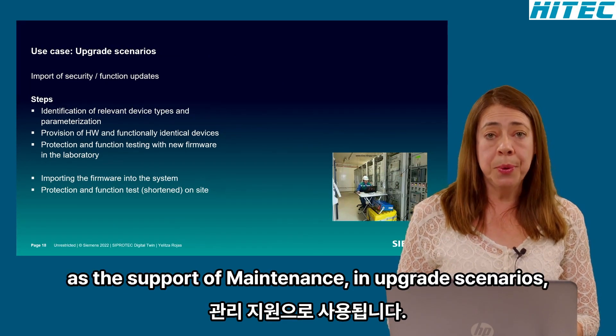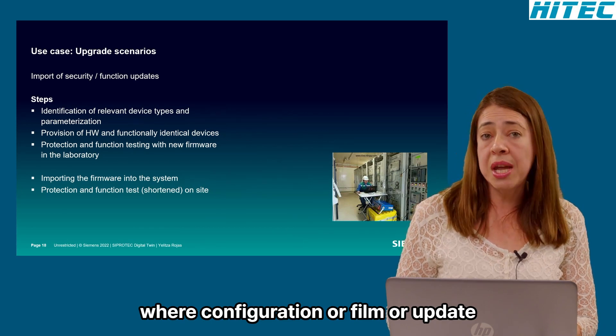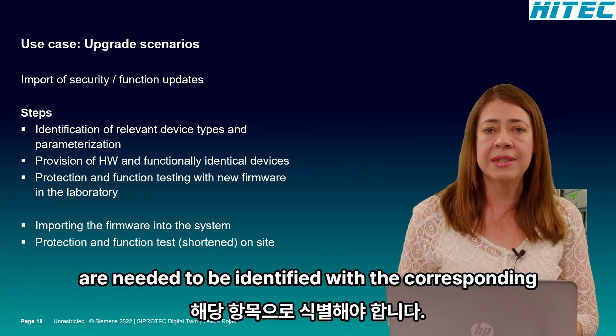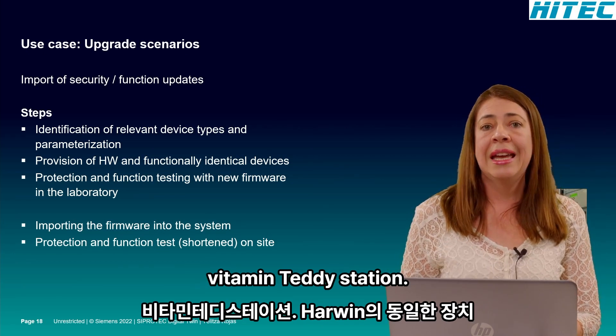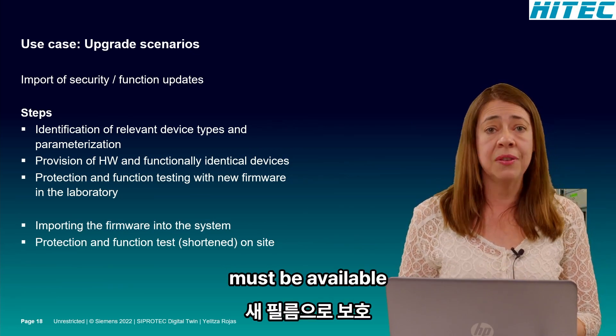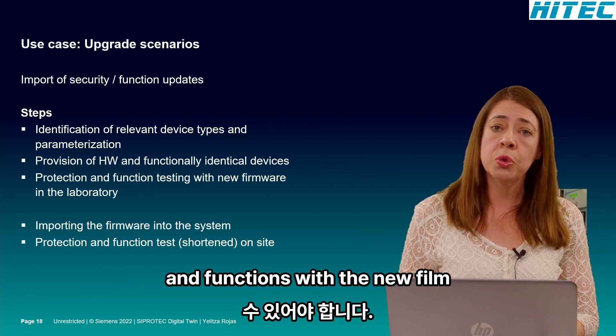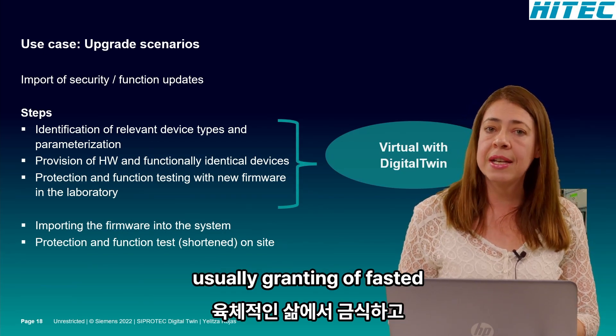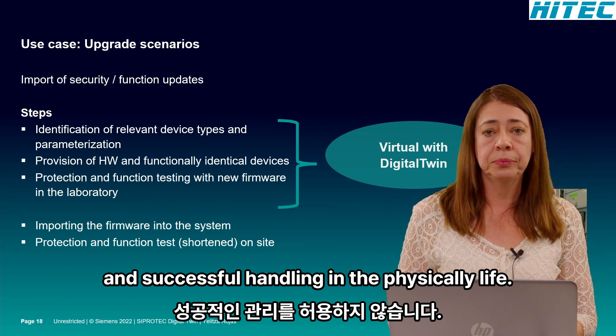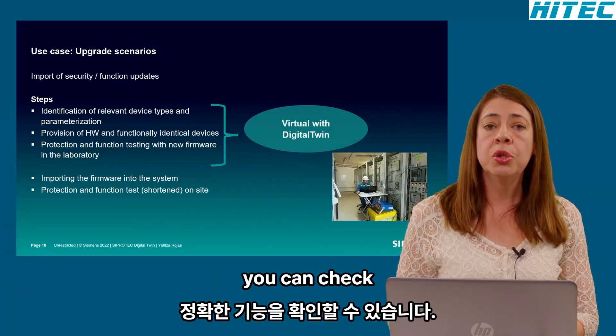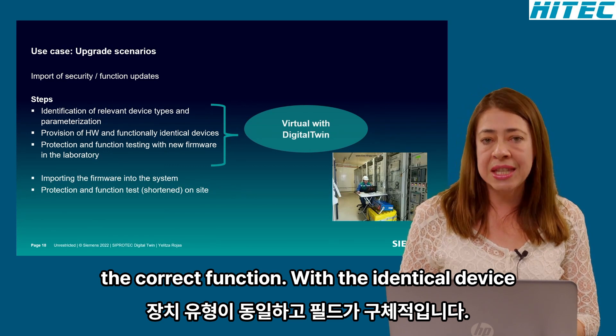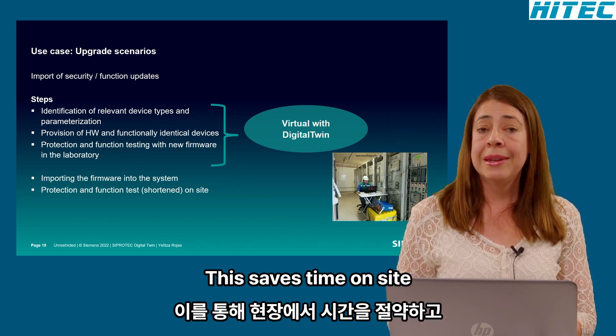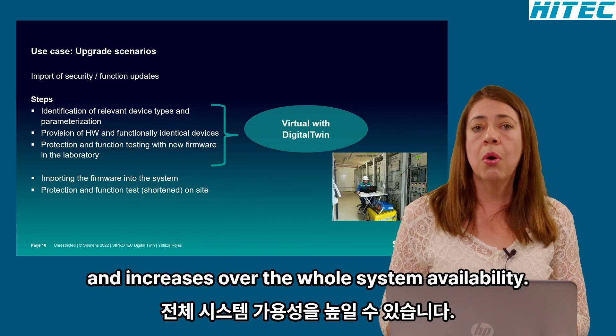The next use case is support of maintenance in upgrade scenarios, where configuration or firmware update is needed in a protection device. Normally, relevant device types need to be identified with the corresponding parameterization, identical devices in hardware and functionality must be available, and testing of protection functions with the new firmware must be run in the laboratory. These steps can be done virtually, granting a faster and successful handling in the physical device. Before installing security or function updates, you can check the correct function with the identical device type and the field-specific parameterization conveniently on the computer, saving time on-site and increasing overall system availability.